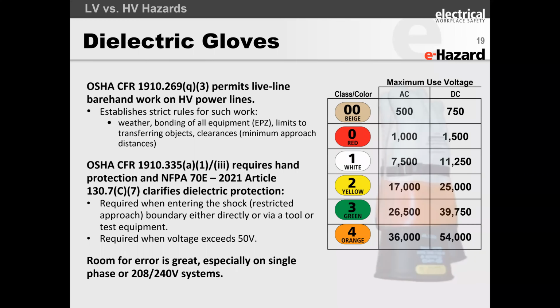Now brace yourself, because this may be shocking to many of you: at high voltage we've got something called a bare hand rule. That means the voltage is so high that you physically do not have a glove rated to work at that voltage. What OSHA allows under this is something called bare hand energized work.